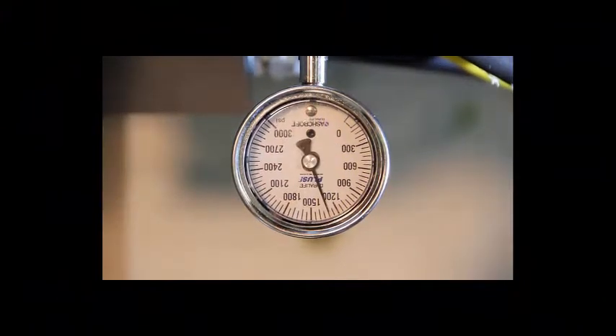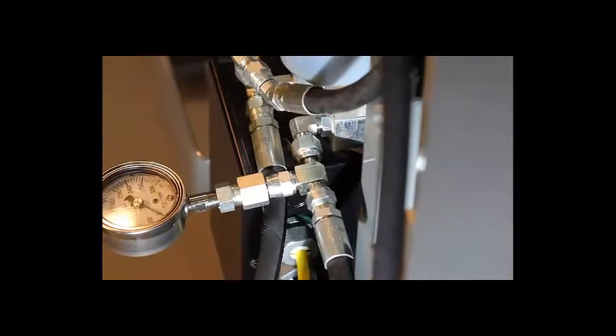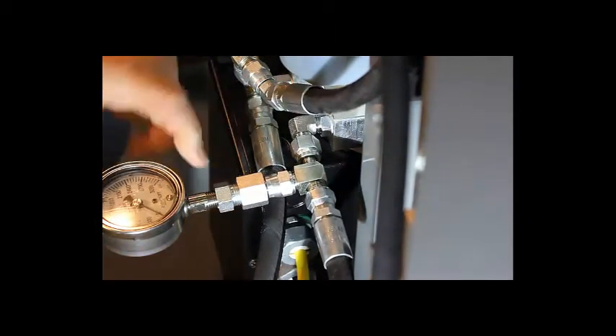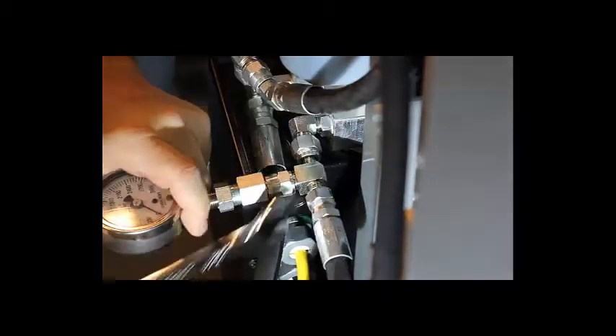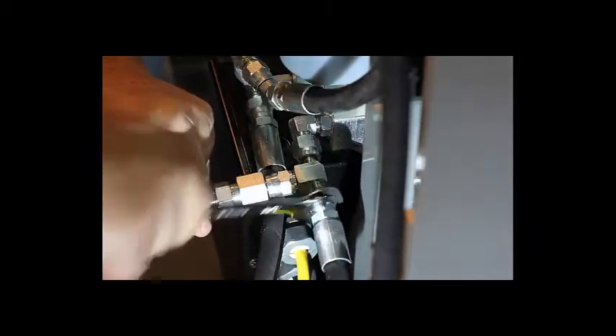This power unit has a plastic tank which normally has an operating pressure of 1125 to 1165 psi. If the system pressure is too low, it will take more than 45 seconds to fully rise from a dock height position. This can be adjusted. Just call your local right height dealer for assistance.